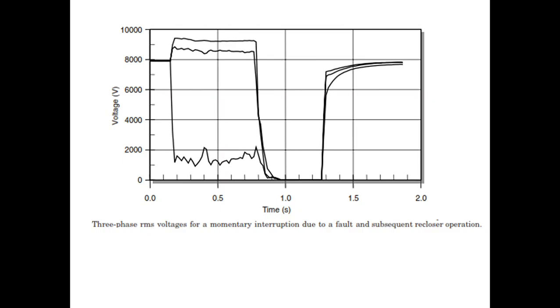This is the three-phase RMS voltage for a momentary interruption due to a fault and subsequent recloser operation. This is simply a graph between time and voltage. Here at 1 second you get a complete loss of the waveform. That is one type of momentary interruption.